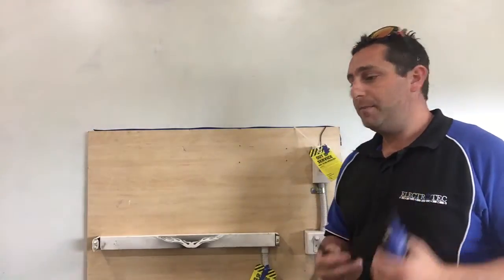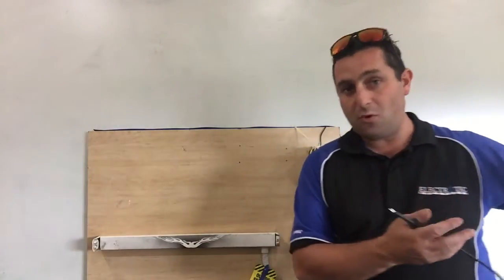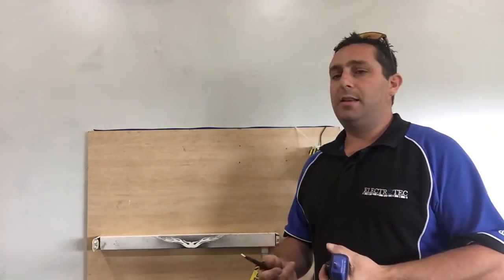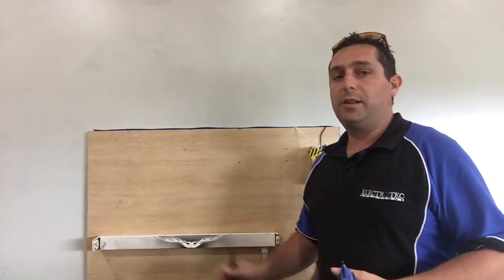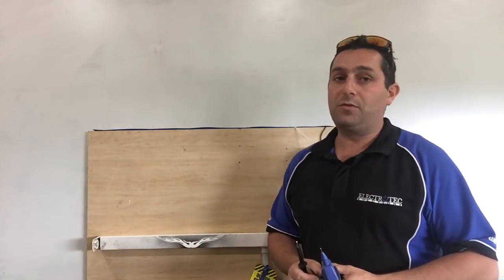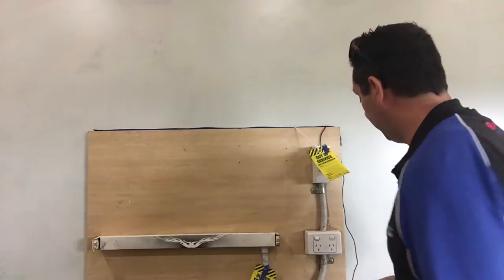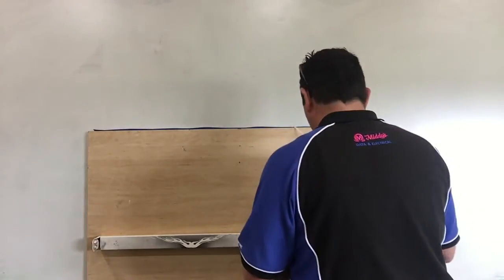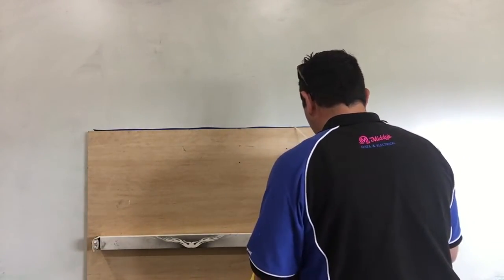When you're out in the workforce, you're not going to leave exposed covers while you walk off and do other things. It creates a really big potential for a hazard. So test our tester: active, neutral, active, earth, neutral, earth. All good. Okay, so we have power there.